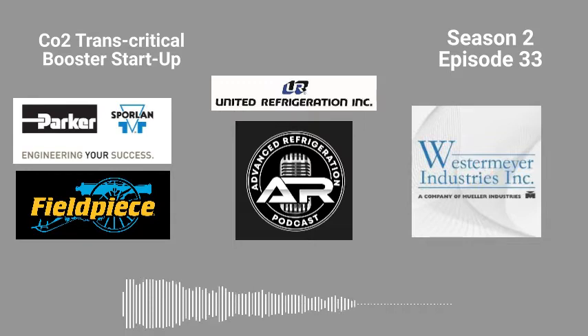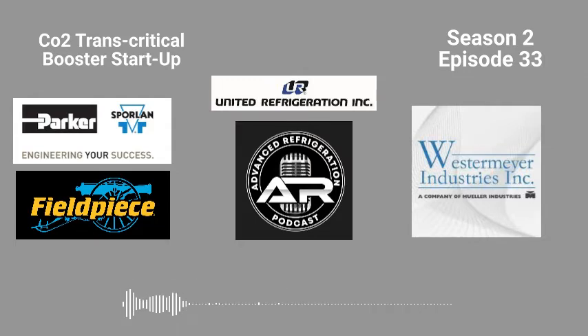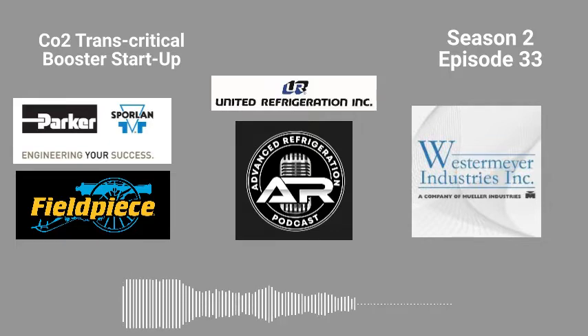So just like a normal rack, you're charging down the liquid line, you're letting it all come back to the rack. I'll usually get 3 balls floating, to the point where the compressors are just maintaining on their own. And then I'll slowly open the low temp switches, get all the low temp compressors on, ready to go. And I will slowly start to bring on the liquid and start letting everything flow. And then I'll start turning circuits on, a few at a time, 1 or 2 at a time.